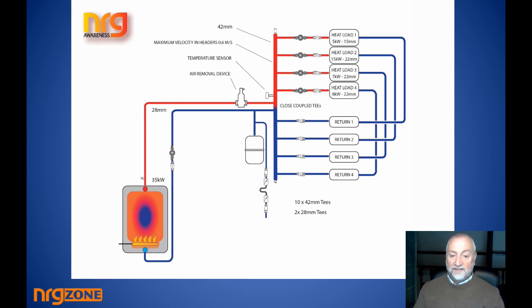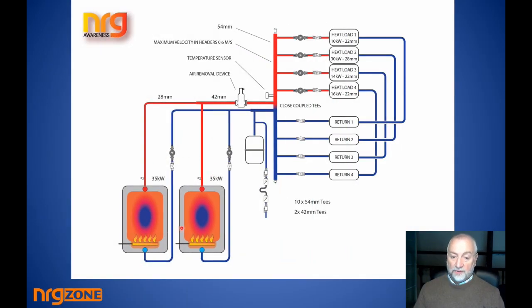If we had a 70 kilowatt boiler output, we might decide that, or with two separate boilers, it doesn't matter. If you had one 70 kilowatt boiler, then the pipe size might be 42 leaving the boilers, 28 from each boiler just getting out of the boiler, into just where you're going to your header, you might have 42, 1.5 inch, but in the header it's always recommended at that kilowattage that you would have 50 mil or 2 inch pipe. So a 2 inch header, 2 inch return header, flow and return. Deaeration again is a very important thing.